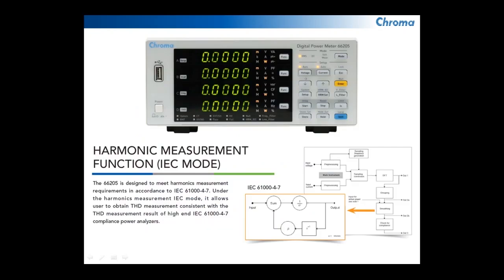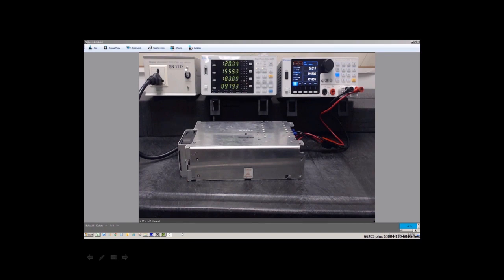When we talk about the harmonic measurement, the IEC 61000-4-7 has a very unique requirement for the method of measuring as well as the accuracy. Chroma has developed this particular unit to make sure that it meets all of those requirements. I've got a unit running behind me here, and on that unit I have a power meter in the center. I've got one of our small DC loads, and I've got a universal box to plug the unit into. And the unit under test is actually just a small switch mode power supply, multiple output, and it does create some harmonic distortion on the input.